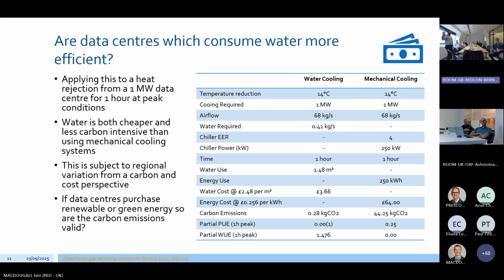On the other hand, if you're trying to do that with mechanical cooling, let's assume a chiller EER of 4, you need 250 kilowatts of power. So if we base that over an hour, the water use is therefore 1.5 meters cubed of water, or 250 kilowatt hours of energy. Which means taking a water cost and an energy cost based on, let's say, London market rates, that ends up being £3.66 of water, or £64 of electricity. So from an operating cost perspective, water is obviously a much more efficient cooling system.